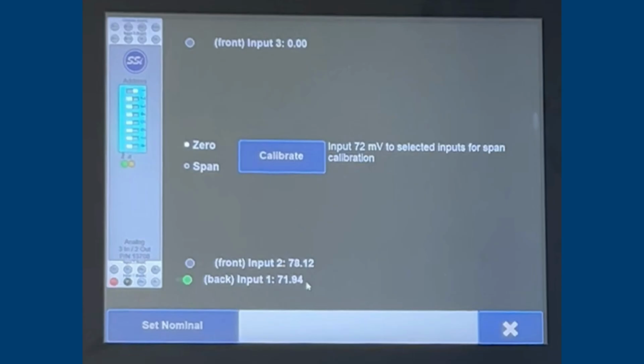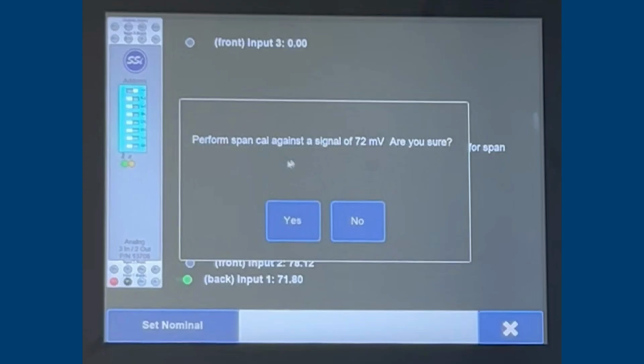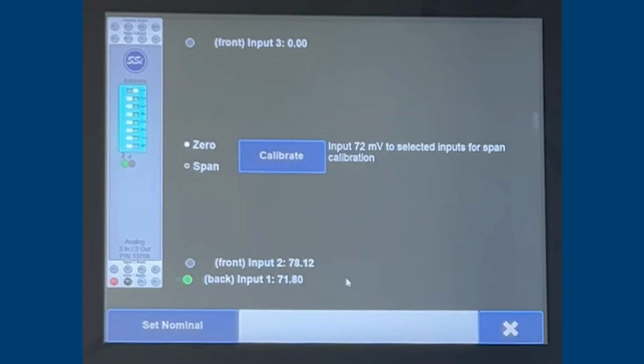If we sourced in 72 and this input read 72 exactly, we have then verified the input is accurate. In this case, it's not reading 72 exactly, so if we'd like to calibrate it, we'd then select the Calibrate button and confirm that we are sourcing in and performing a span calibration, 72 millivolts. Click Yes, and we let it process. The whole purpose of this is to verify the input is reading accurate. Once the calibration process is complete, you then give a couple seconds for the input to update. It is now reading 72 millivolts. This is the 0 and span of the input.